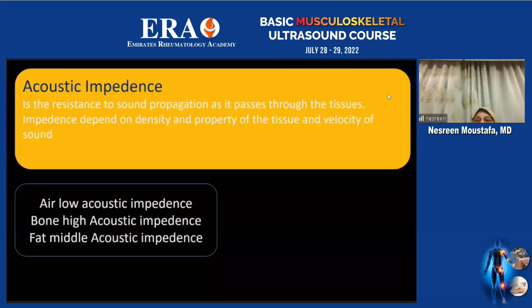We'll also talk about acoustic impedance. Acoustic impedance is a very important concept. It is the resistance to sound propagation as it passes through the tissue, and impedance depends on the density and property of the tissue and the velocity of the sound. We have different kinds of tissue, and the sound can be reflected or refracted, but it depends on which tissue is adjacent to another. So if I have air, it has a low acoustic impedance. If I have bone, that is the highest one. So this will also affect the refraction or reflection of the sound.